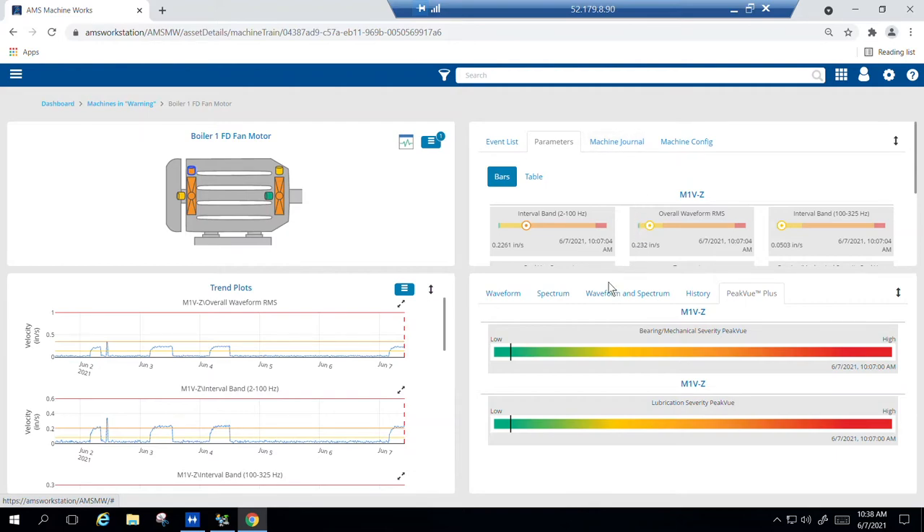In the bottom right, we can quickly view any collected waveforms or spectra, as well as the PeakVue Plus indicators we mentioned earlier to detect bearing and lubrication faults. On this machine you can see we have high vibration based on the orange alert levels. We're currently looking at the outboard bearing. The marker on the PeakVue Plus indicator bars is in the green area, indicating that currently there are no bearing or lubrication issues, so something else is causing this vibration. Our first interval band for low frequency around turning speed is showing the highest alert level, potentially indicating an imbalance.